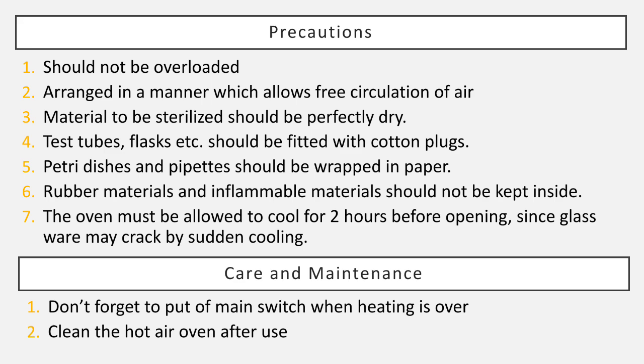The oven must be allowed to cool for 2 hours before opening. This is a very important step, since glassware may crack by sudden cooling. So, what are the care and maintenance? Do not forget to switch off the main switch when heating is over, and clean the hot air oven after use.